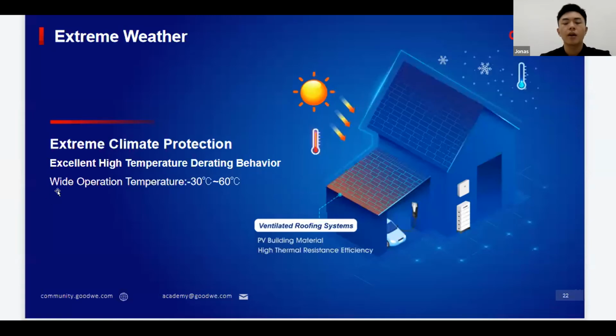Like I just mentioned, the environment can affect the inverter and the PV module. If the environmental temperature, for example, becomes very high, the inverter is likely to start losing efficiency. It's like the over temperature protection. If the temperature is very high, the inverter will start derating. That is a self-protection mechanism.